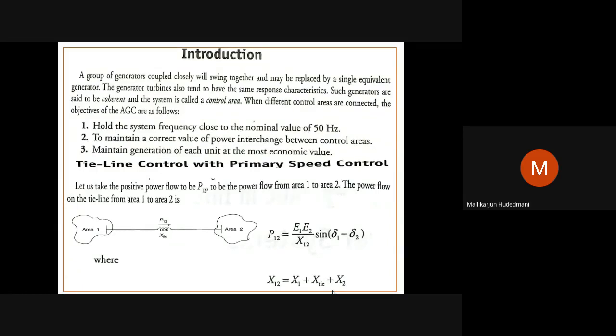Similarly, it is connected to area 2. Let us say there is another bus which is interfaced with the tie line. E2 angle delta 2 be the value of that. Then the total transmission line reactance between them, X12, is the total reactance of the path starting from the generator: X1 from its reactance, X tie line, whatever the reactance, and X2 of generating area 2. When I interconnect, that becomes the total representation.